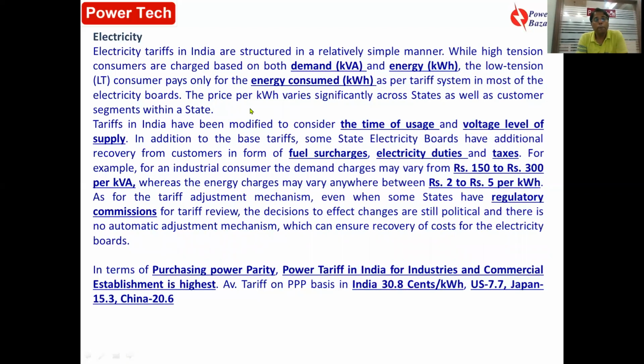For industries, charges are based on demand. Suppose I have to meet a demand, I tell the distribution company my demand is 1 MVA or 1 megawatt. That means I am booking that whenever I require 1 megawatt, they give me, and I am ready to pay demand charges for that. I have fixed a demand. Suppose I don't use any energy, then I pay 0 energy charges, but I still have to pay fixed demand charges.